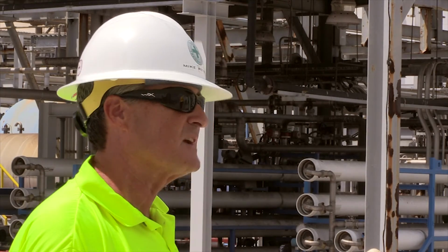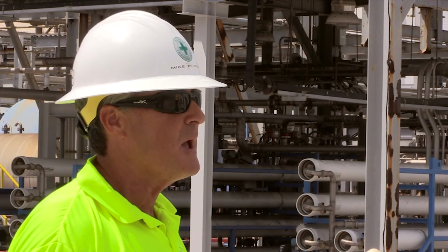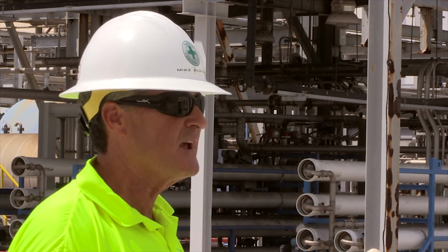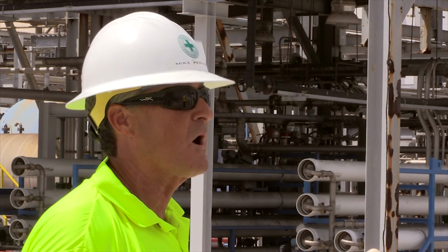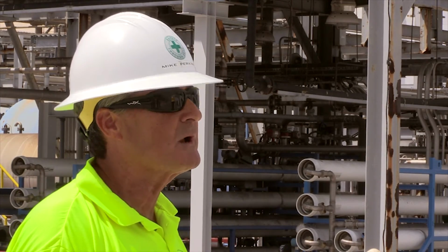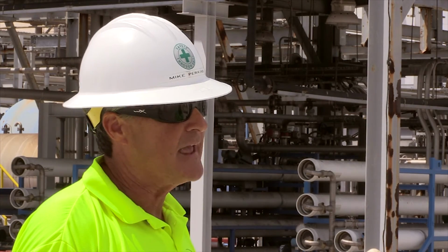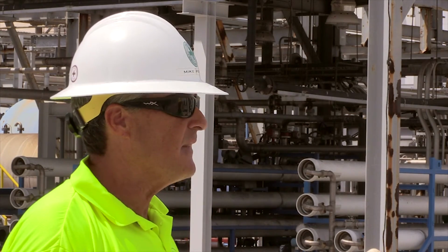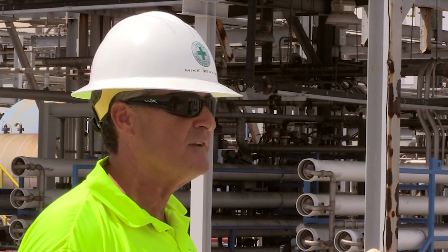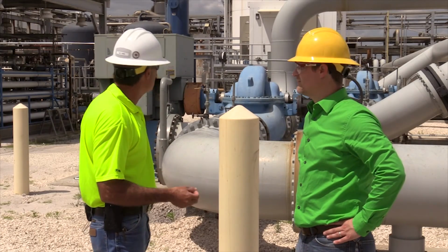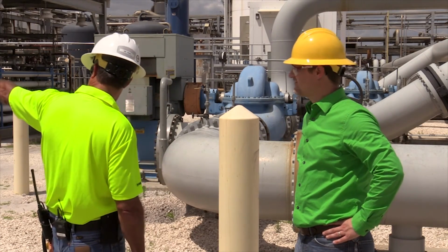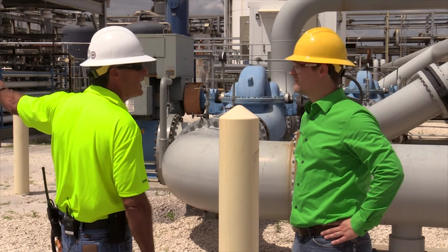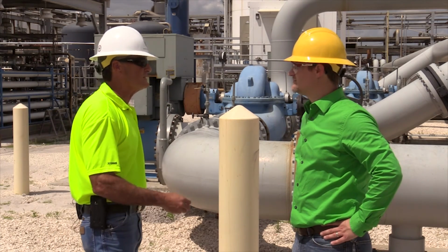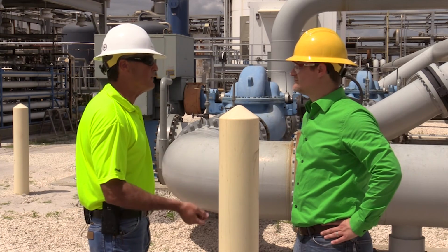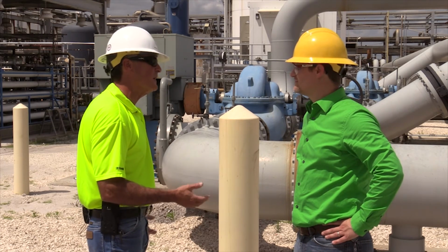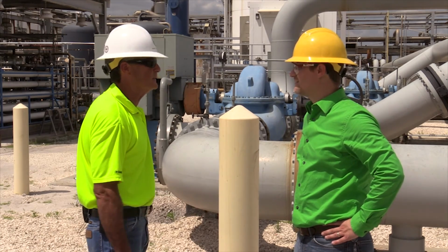They're tightly wound spiral filters, and using high pressure you push the water through, which makes it pretty clean when it comes out, removing all the anions and cations. But that water's still not clean enough for what we want for steam, so we run it through our demineralizer to pull out everything else. That water comes out ultra pure, as clean as we can make it, and that's what we use to drive the steam turbine.